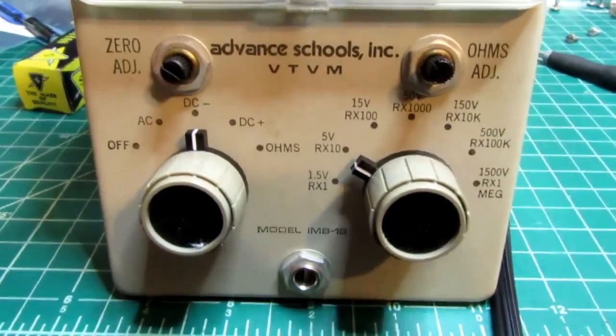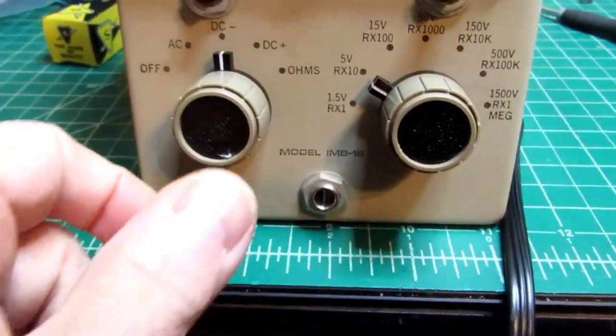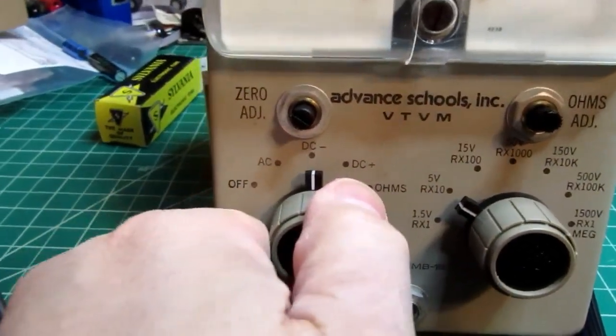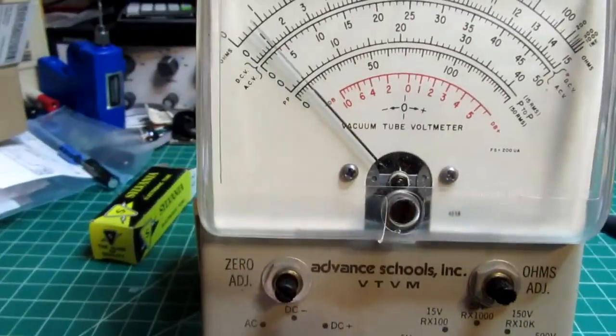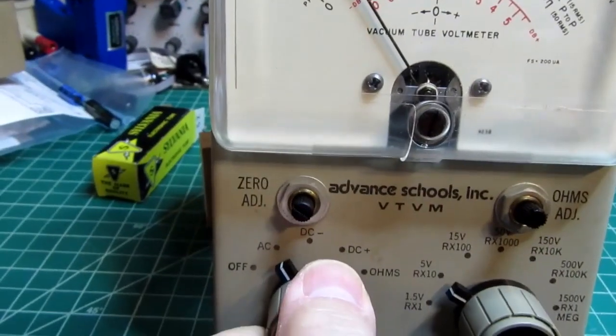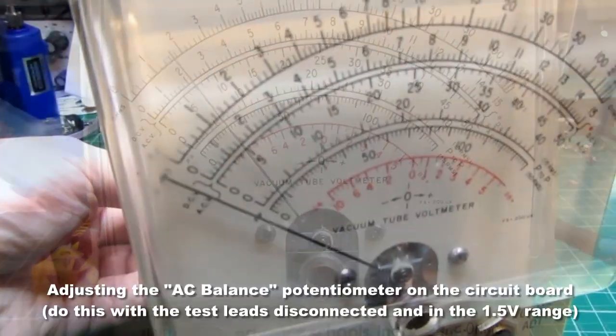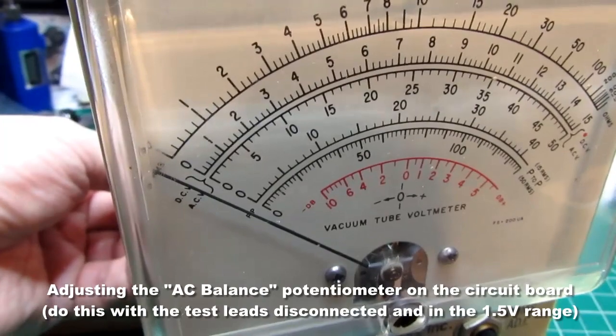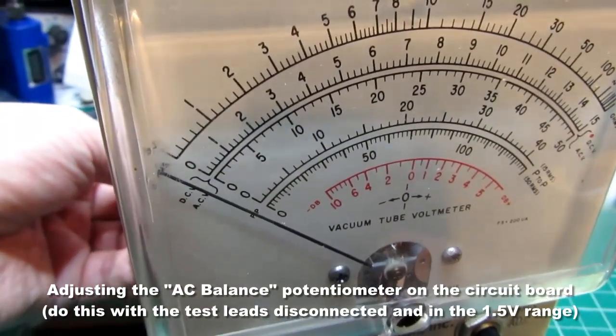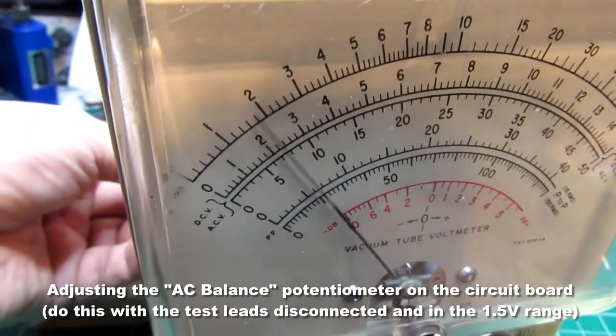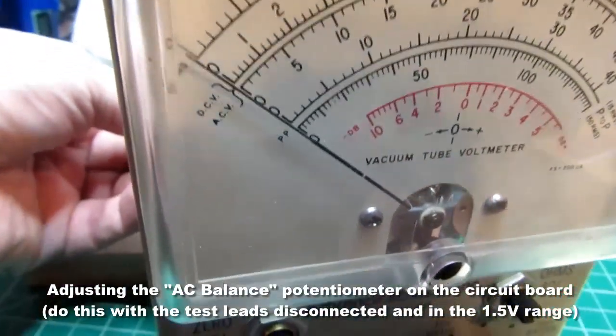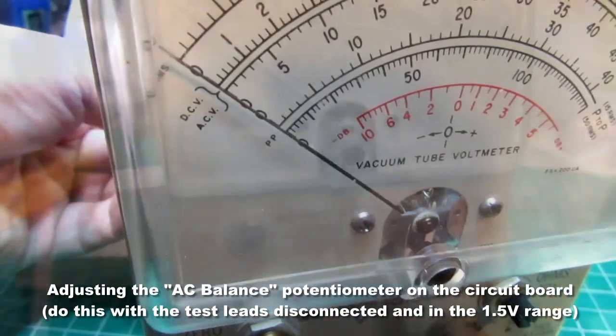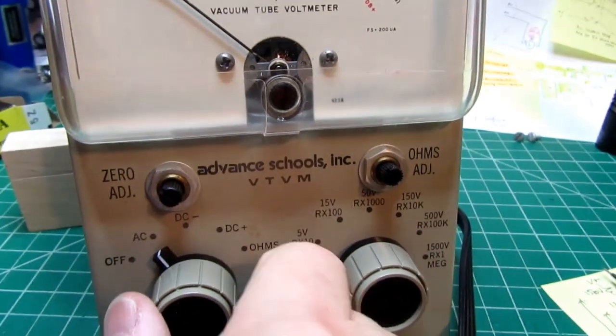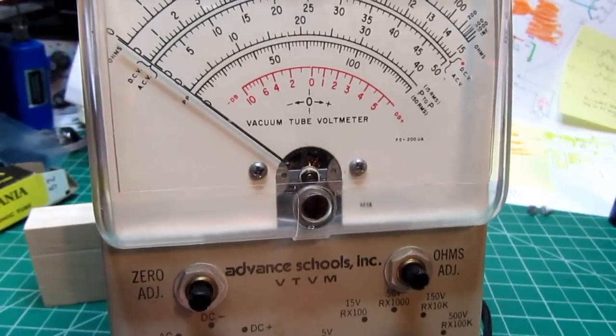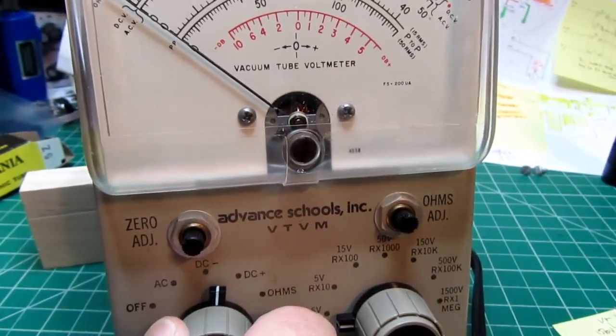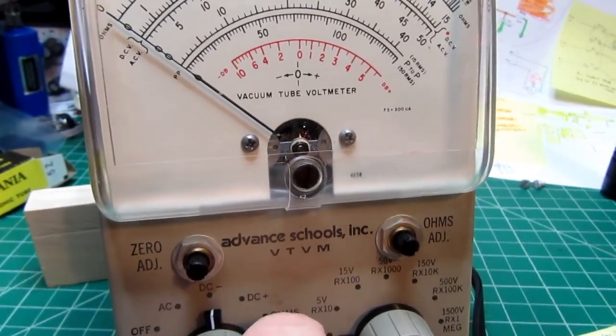And then unplugging the test leads, if I go to the AC position, that's a pretty big deflection. Okay, here's adjusting the AC balance. Should be getting it to right about 0. And when I go back and forth between there and DC minus and DC plus, the meter shouldn't move much.